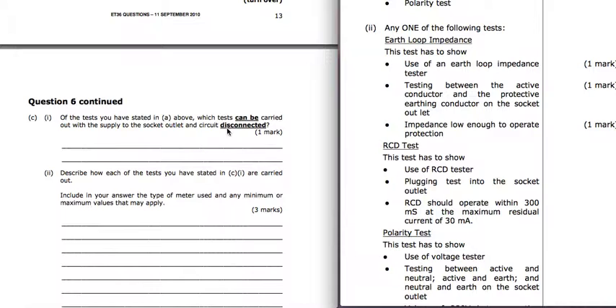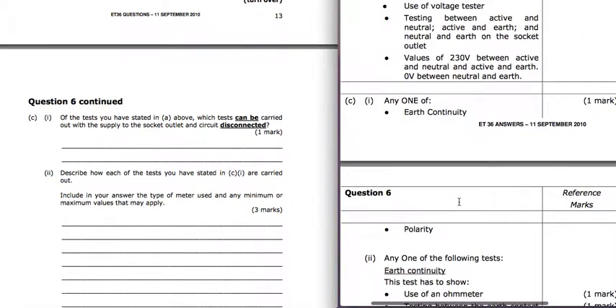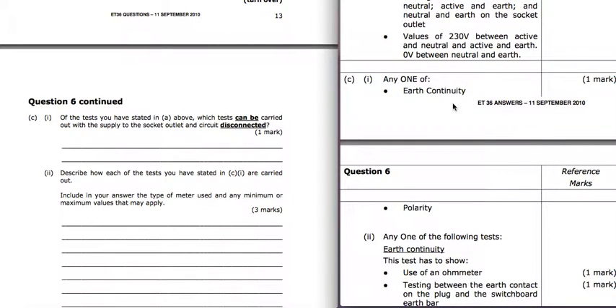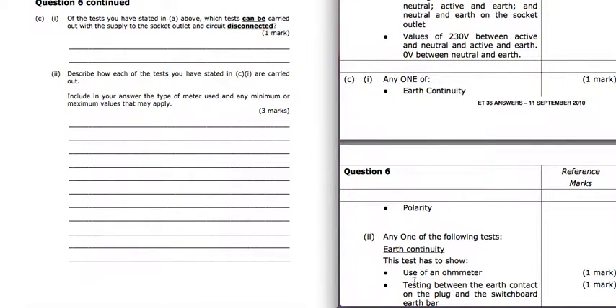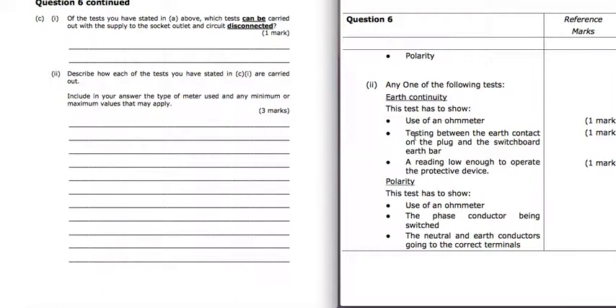Part C is looking for tests that you've got to carry out once it's been disconnected. So these are going to be your earth continuity or your polarity. And again, you're asked to describe one of those here. I think I'll be looking at earth continuity, using an ohm meter, testing between the earth at the plug and the switchboard earth bar, and looking for a reading low enough to operate the protective device. So it's not 1 ohm or half an ohm or anything like that. It's just a reading low enough to operate the protective device.